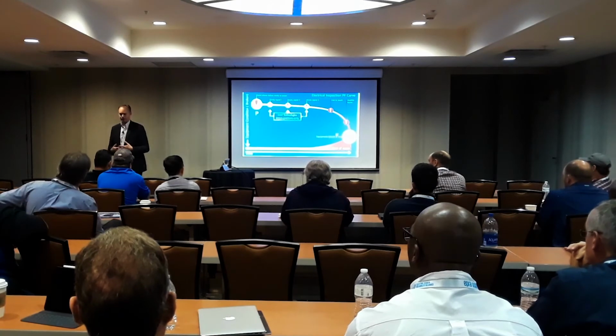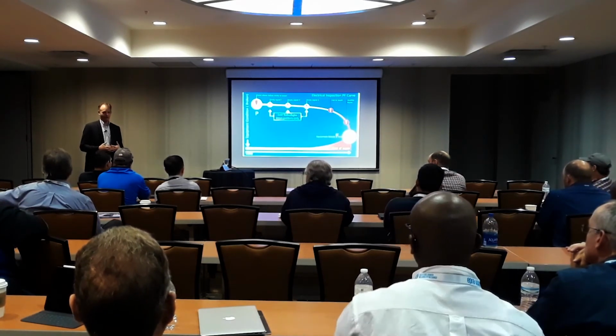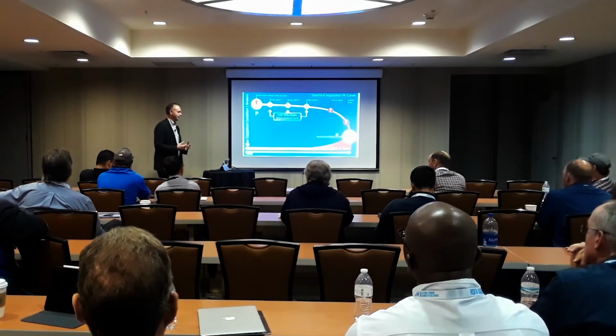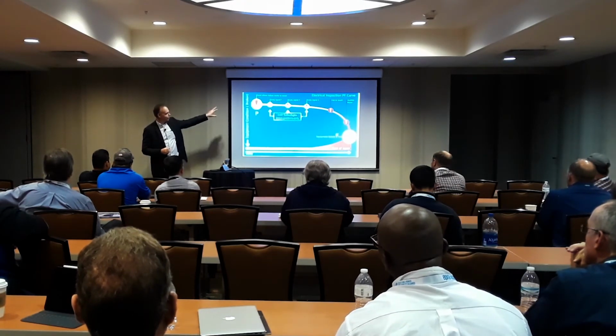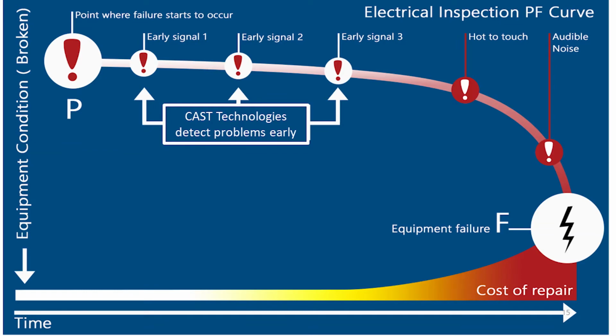We had a shipping split. They were supposed to put it back together again and torque the bus bars to a certain level, and they just never did. And it could run like that actually for years, but eventually it's going to cause a problem. So there's all kinds of things that can happen. Anyway, coming back. Early warning signs, they will get more distinct the further you go down this PF curve.